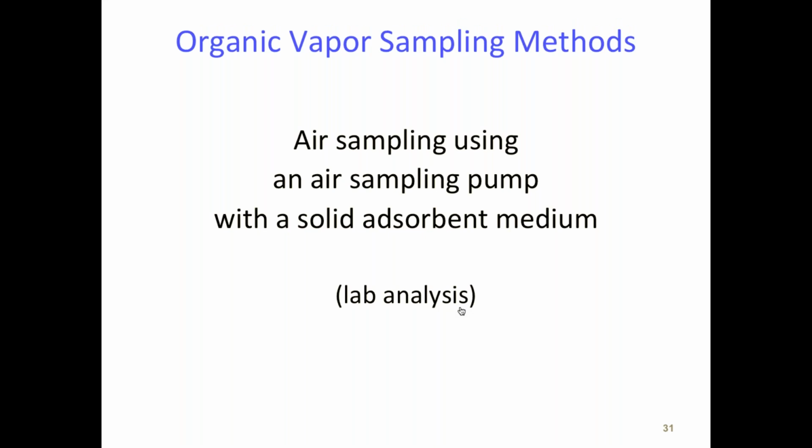Some of the techniques may ask you to also put a sorbent on here for moisture. In fact, some of these Draeger tubes that we have, you may have noticed that they're multi-section, and those first sections might be to take moisture out. It might also be to remove chemicals in the air that are confounders that would also change the color of the tube that are not the target gas, right? So sometimes you have to do something to protect it from that. So yeah, that's called breakthrough.